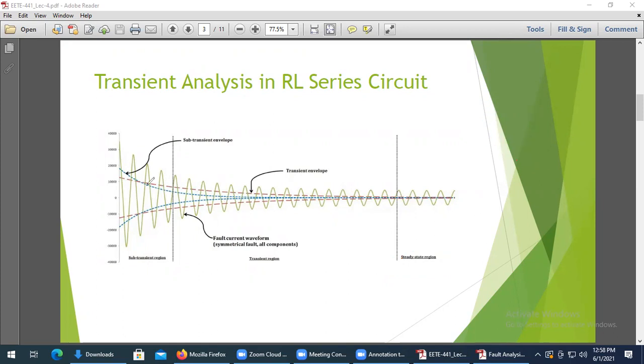So we can summarize the statement like this: at the very beginning, the fault current becomes high. Now how long will this fault current continue? After a shorter period of time, the fault current starts to decay. This very high magnitude fault current sustains for half a cycle to 1.5 cycles maximum. It has been observed that it clears, or the magnitude reduces, within 2 cycles, or in some cases a maximum of 3 cycles, but generally this maximum value continues for a maximum of half a cycle of the frequency.